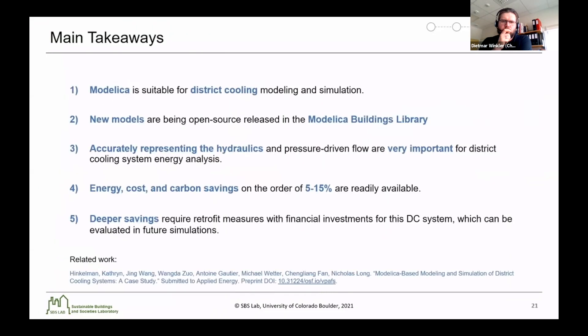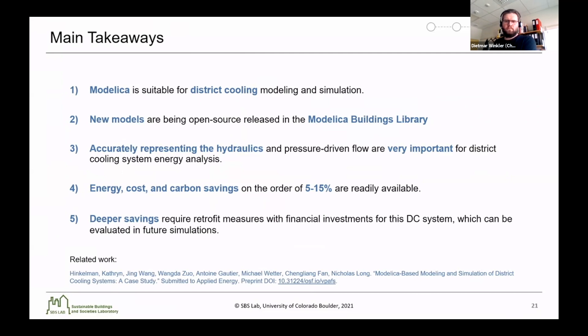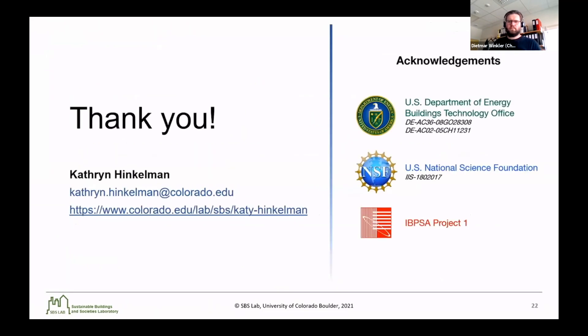In conclusion, some main takeaways: first, Modelica is suitable for district cooling modeling and simulation; second, we have open-source released new models in the Modelica Buildings Library that can be used for future case studies; third, accurately representing hydraulics and pressure-driven flow are very important for district cooling system energy analysis. For this case study, the energy cost and carbon savings were on the order of 5% to 15%, and these are readily available without requiring financial investments by the district. However, deeper savings are possible but do require retrofit measures with financial investments, which can be evaluated in future simulations. Thank you very much, and I'd like to acknowledge our funding agencies including the U.S. Department of Energy, U.S. National Science Foundation, and IBPSA Project 1. I look forward to your questions and conversations during the Q&A.